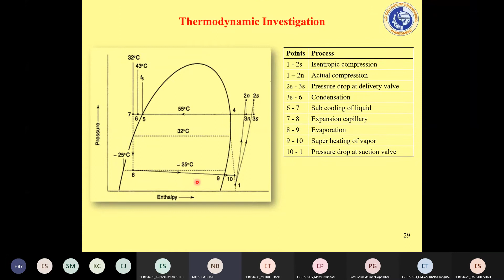So the thermodynamic investigation has been done for a Samsung make RT31M model refrigerator. By contacting the manufacturers, we got certain information regarding the compressor. Of course, certain information is also available on the compressor, but not all. So you have to contact either compressor manufacturers or the refrigerator manufacturers to get certain details. It's a 310 liter refrigerator having a compressor capacity of 175 watt, and these are certain numbers based on the 10-point cycle. Its rotational speed is 2090 rpm and it works on Indian conditions, so 210 to 250 volt input and 50 hertz frequency.